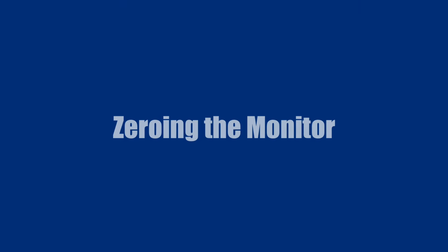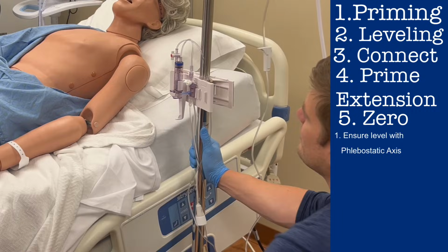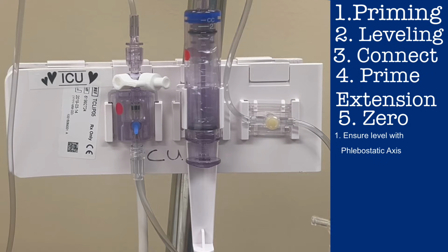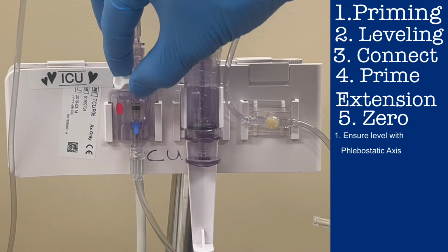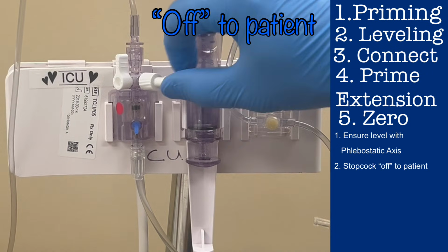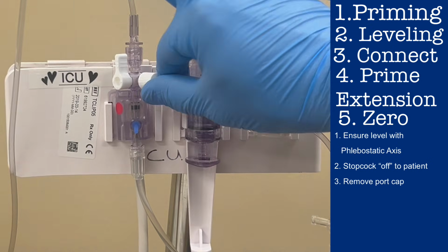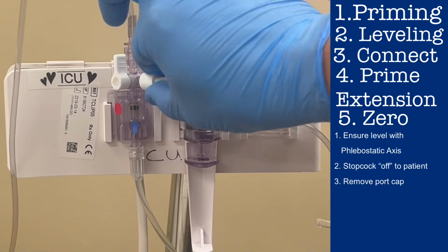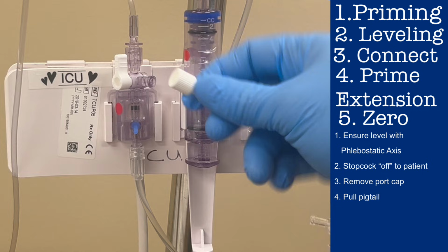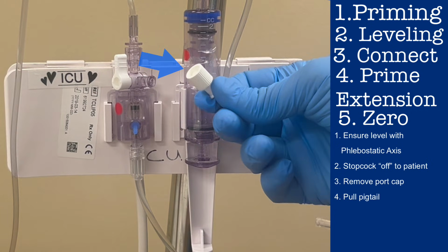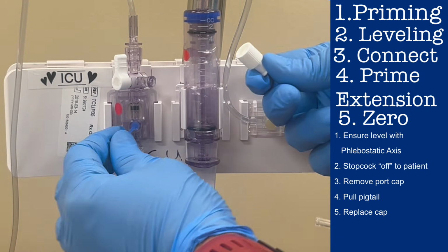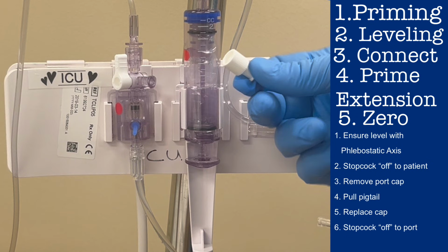As previously stated, you should see a waveform when you connect to the patient, but you'll need to zero the system to get an accurate arterial pressure reading. Ensure the transducer is still level and in line with the phlebostatic axis. Go to the transducer. Turn the stopcock off to the patient by turning the lever up. Remove the cap from the side port on the transducer. Be careful to maintain the sterility of the inside of this cap until you replace it. Pull the pigtail to drain a small amount of saline.